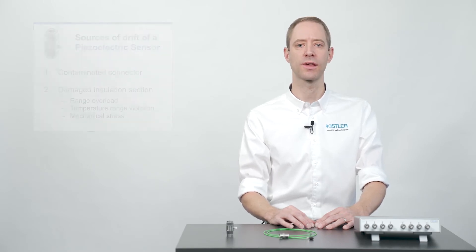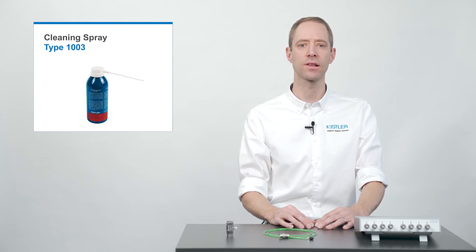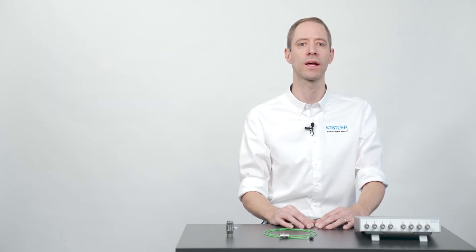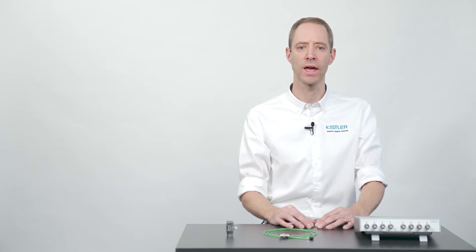For the piezoelectric sensor, the most common source of drift is a contaminated connector which reduces the insulation. The contamination can be caused by any kind of dust, dirt or liquids such as oil. For such cases, Kistler offers a special cleaning spray to remove the contamination. To prevent contamination of the connector, it must be protected with the supplied caps when no cable is connected.